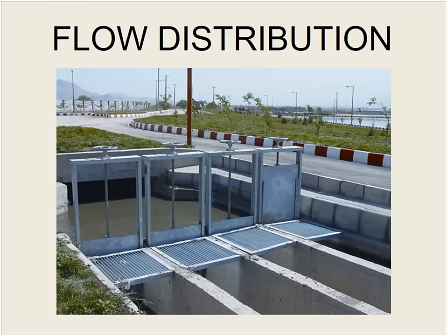So we talked about velocities through a collection system being generally at 2 feet per second. We're still at that level as we come into the plant. Now the plant will have multiple units for treating, and the reason for multiple units is you want everything to run within certain parameters. So I may need a lot of units online during a high rain event, and I may need very few during August when I haven't seen rain in 6 weeks. So we have to have some method of controlling our flow distribution through the plant, so we run in those ideal ranges all the time.